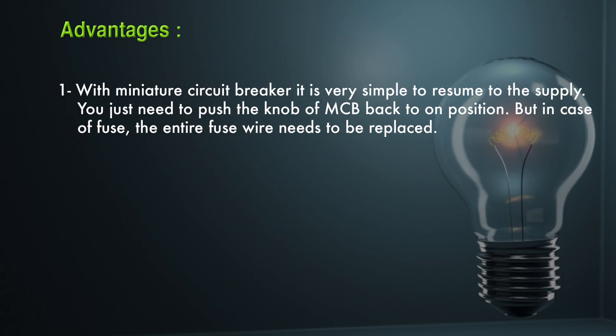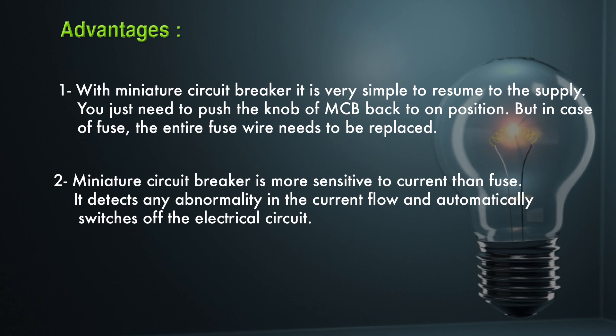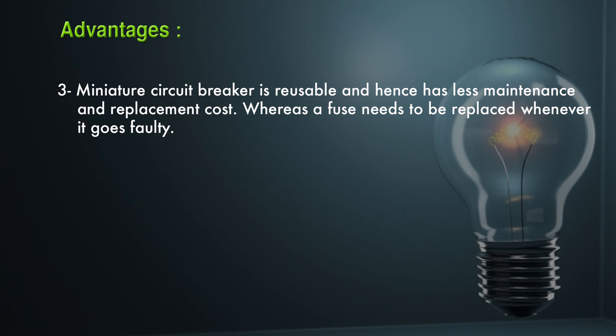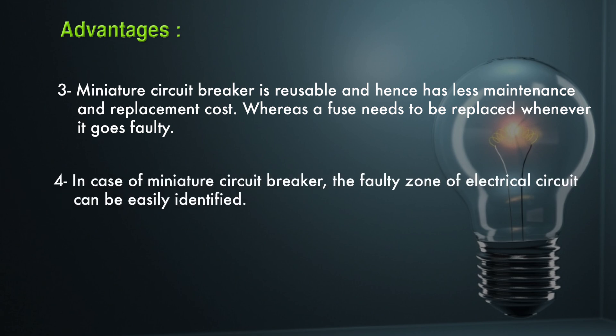The advantages of MCB over fuse are: it is very simple to resume supply — just push the knob back to on position, whereas with a fuse the entire fuse wire must be replaced; MCB is more sensitive to current than a fuse and automatically switches off upon detecting any abnormality; MCB is reusable and has lower maintenance and replacement cost; and faulty zones of the electric circuit can be easily identified with an MCB.